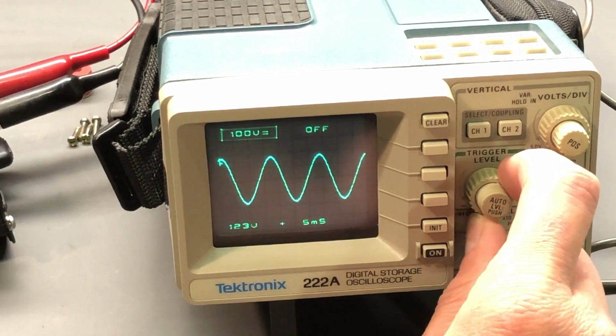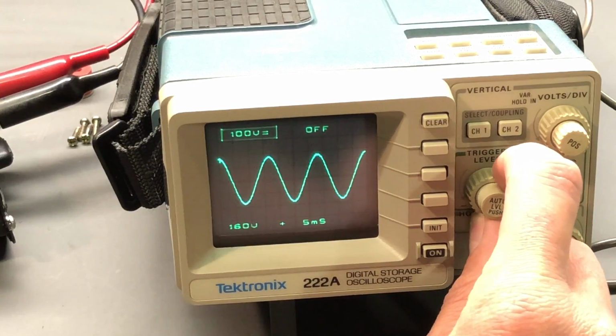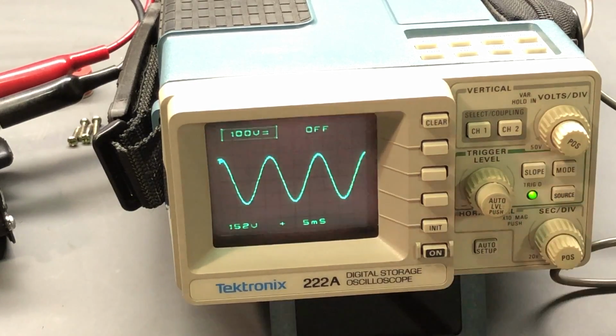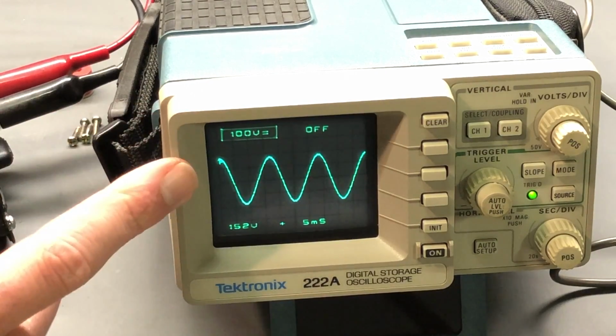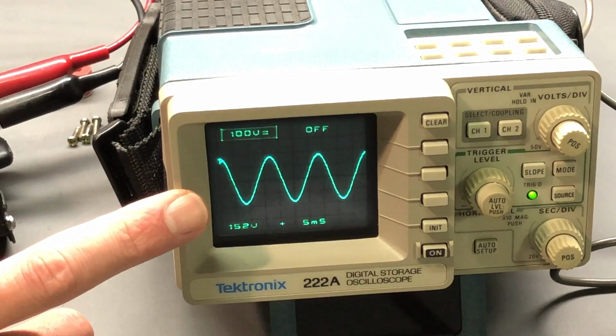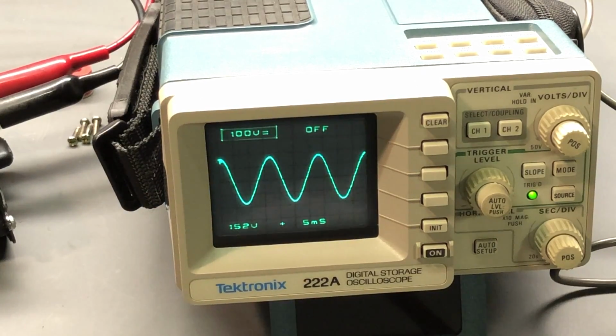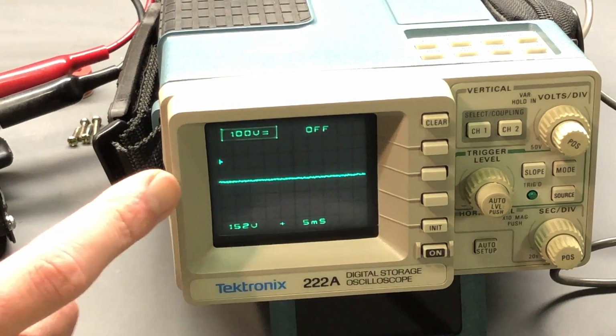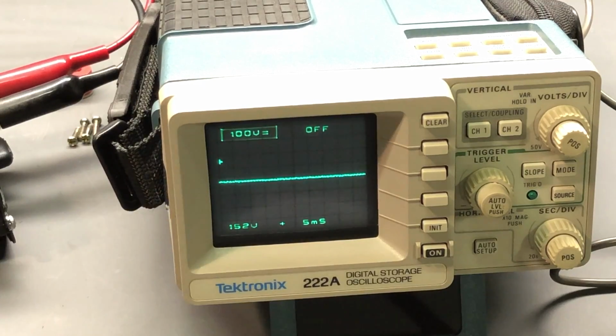What I can do is place the trough right there, like that, that'll be fine. So that waveform is looking very good, no issues with that. It looks like there's equal deflection or amplitude above and below the center ground reference. So if I turn the inverter off again, you can see this represents ground right in the center on the trace there with no signal. So we want to see an equal amplitude above and below that.